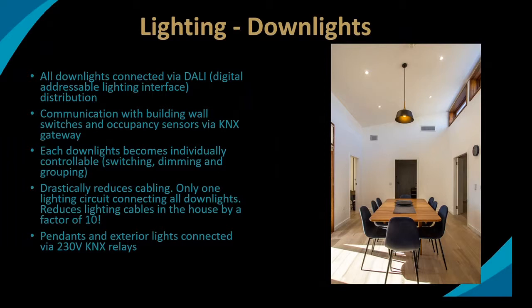In a traditional house, if you wanted to operate a certain group of lights, one cable would have to go to your dining room and back to a relay, same with your kitchen, living room, etc. For our house alone, by using DALI, we're able to reduce our lighting cables by a factor of 10. Especially for the construction and reconstruction work we're doing in Dubai, being able to connect just one circuit for lighting in the house, as opposed to an additional 10, is a real time saver for us. So that was a real advantage.